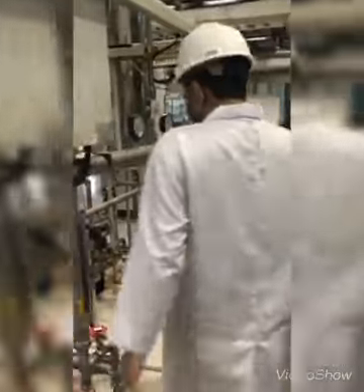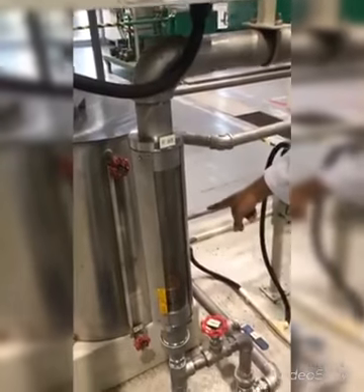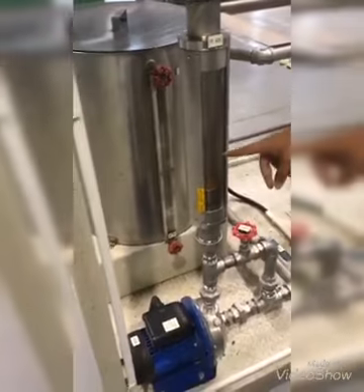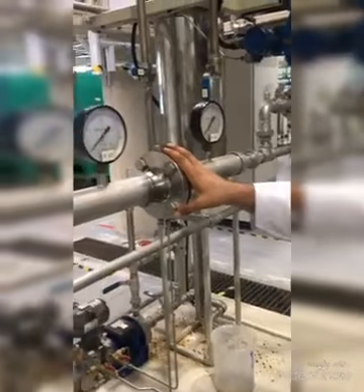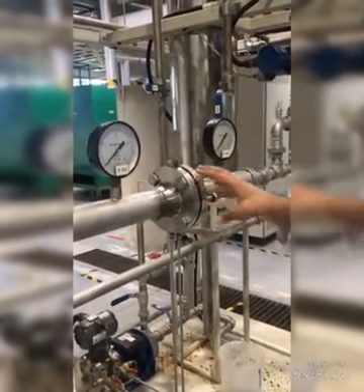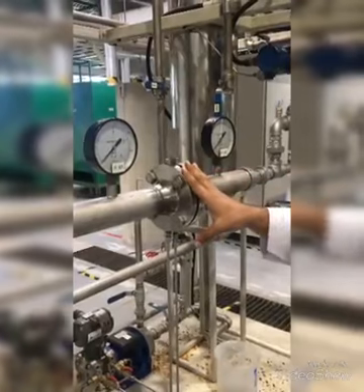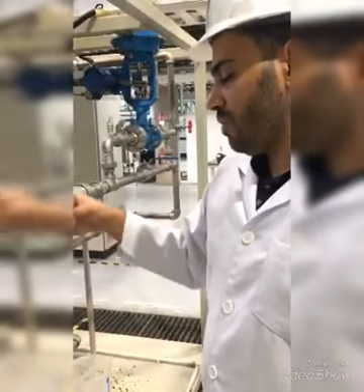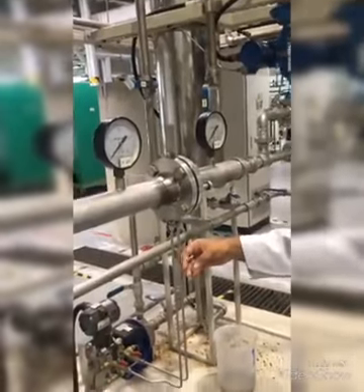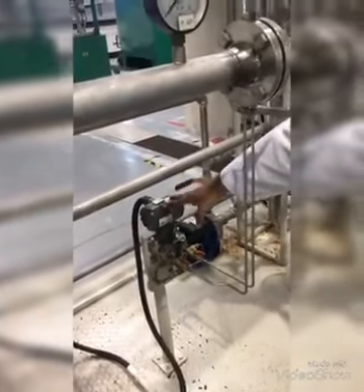and also we have the fluids come from the source to the tank, then the fluids go from the bottom to the circulation pump, then it goes to the flow indicators, after that to the orifice. The function of the orifice is to restrict the flow and also to restrict the pressure and decrease the pressure from high to low. Then the orifice will send the signal to the flow transmitters. Then flow transmitters will send the signal to the control panel.